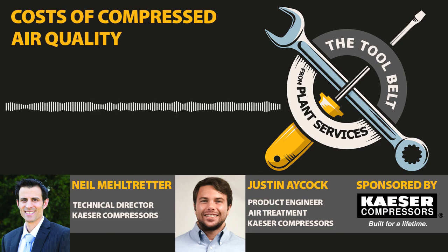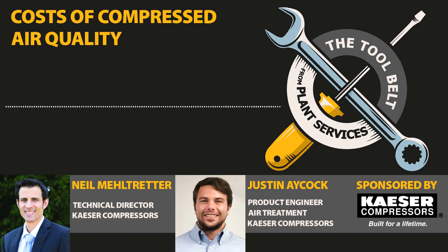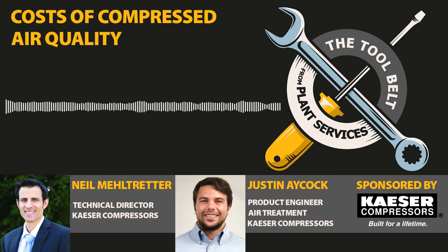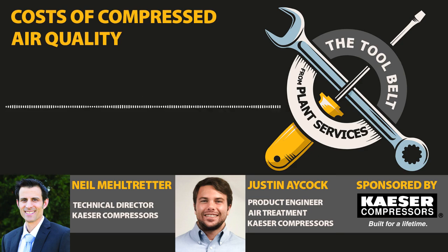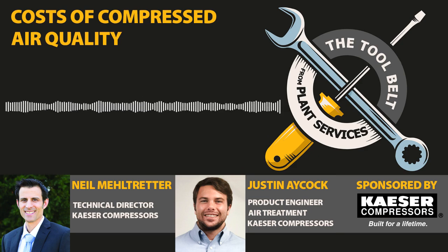system piping. We go into plants and we see piping that may be endemic from the startup of the facility, and some of these facilities are 30, 40, 50 years old. I've seen certainly some receivers that are older than I am, which as long as you're having the inspections done, that's necessarily fine.